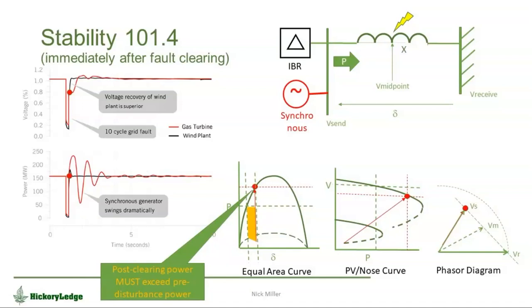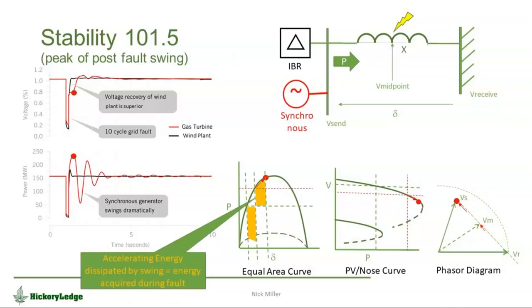So we go on to this, and this is now at the peak of the power swing. All right, so the angle has moved further out. We're up that sine wave, that half a sine wave. And at the point where the excess energy dissipated by having that angle be greater than, and the power be greater than that being pushed into the drivetrain by the turbine, the machine stops accelerating and decelerates and proceeds to bounce around, hopefully in a damped fashion.